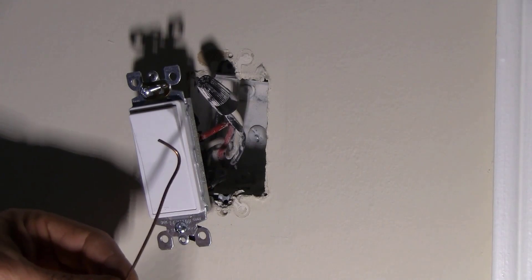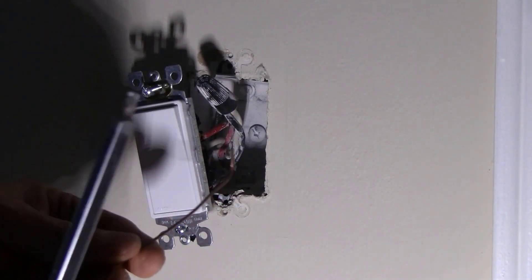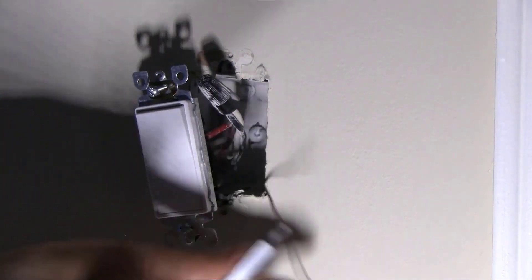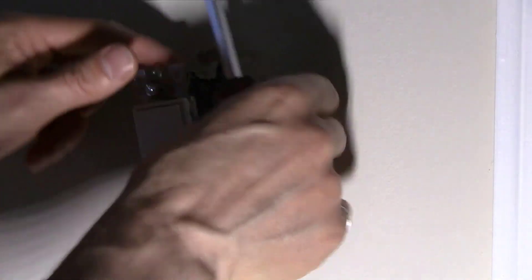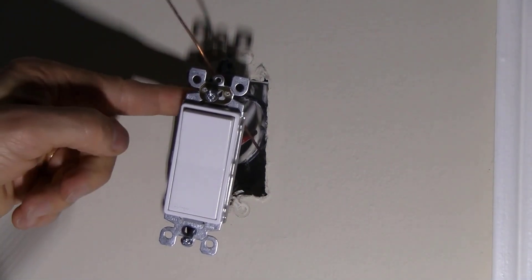I've got a piece of wire here that I'm going to use. I'm going to unscrew this other screw here. Because I've bent this and I'm going to have it go up, I'm going to put it on the left side of the screw because that's the correct side so that the screw pulls it in when it's tightened. I'm going to snake that in there, tighten it up so we make sure it's tight. The ground screw on this particular switch is over on this side, so I'll go ahead and connect this wire to that ground screw.